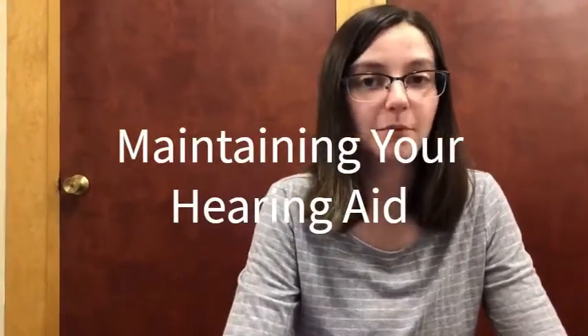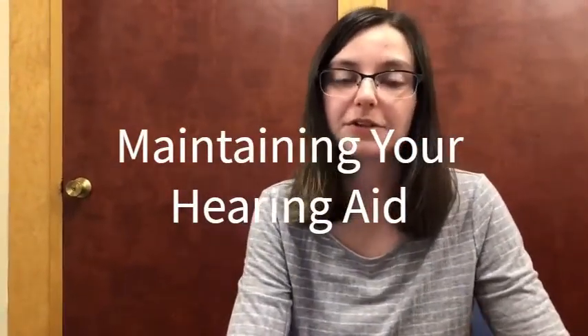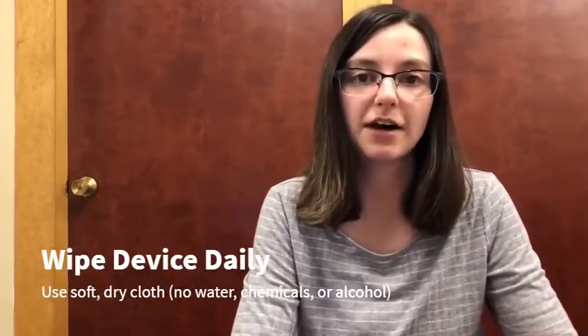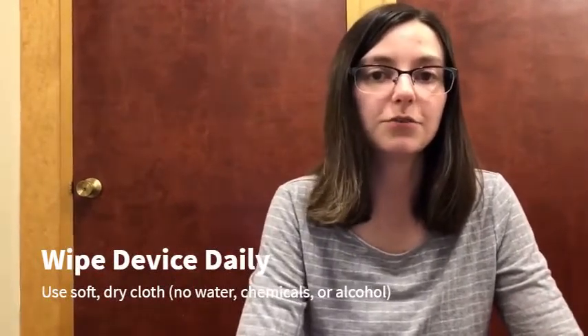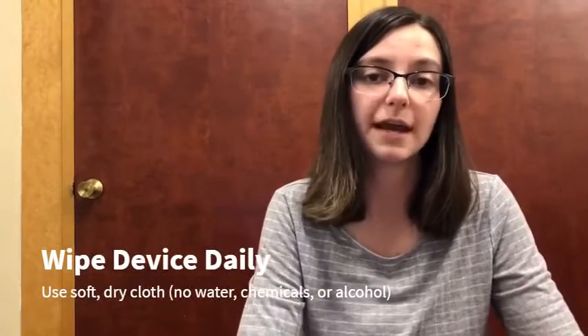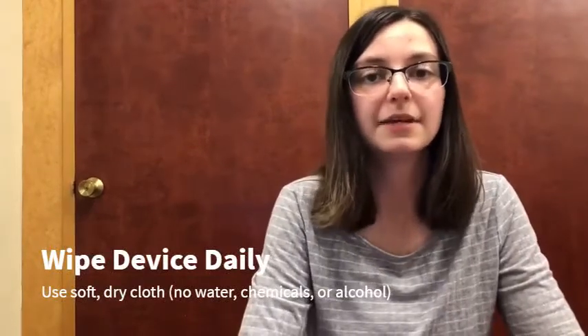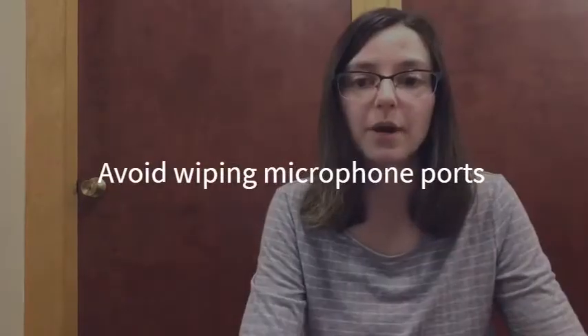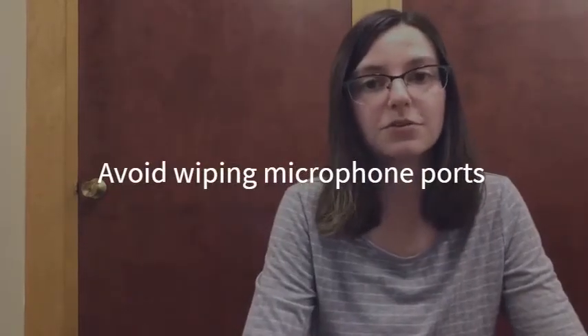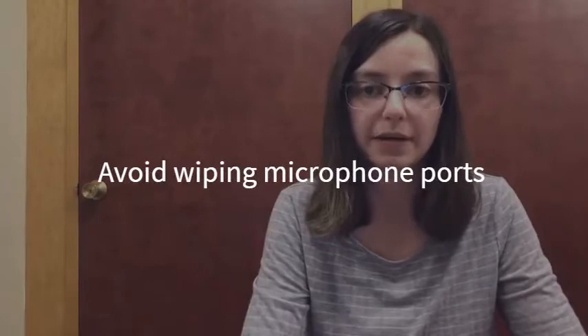Now we'd like to give you some pointers for the maintenance and well-being of your hearing aid in order to ensure it lives the longest life possible. First, here are some tips for cleaning. You should wipe the device daily with a soft, dry cloth. You'll want to avoid using any wipes with water, chemicals, or alcohol when cleaning because these could cause damage to your hearing aid. Make sure you also avoid wiping any microphone ports in order to prevent the spreading of debris.